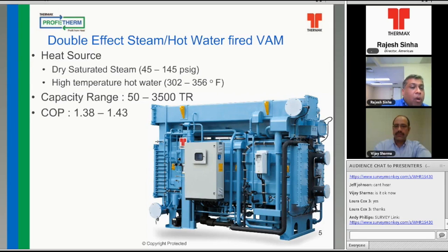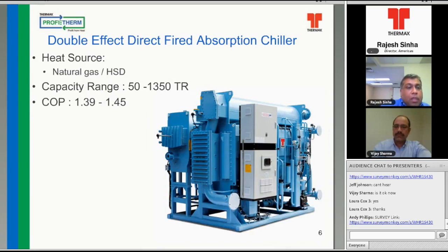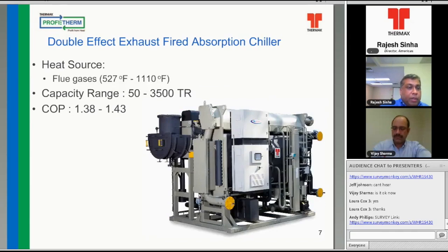Moving on, we have the double effect steam or hot water driven absorbers. These run on dry saturated steam of 45 to 145 psig steam pressure, or it could be high temperature hot water from 302 to 356 degrees Fahrenheit. Even this has a capacity range of 50 right up to 3,500 tons and a COP range of 1.38 to 1.43. The double effect direct fired absorption chillers could be run on natural gas or high-speed diesel, that is number 2 oil, and it has a capacity range of 50 to 1,350 tons, and the COP range is between 1.39 to 1.45.